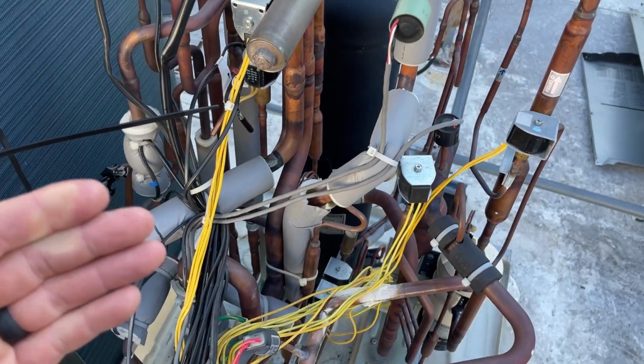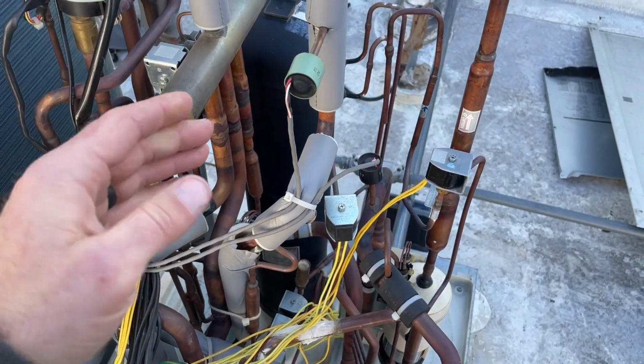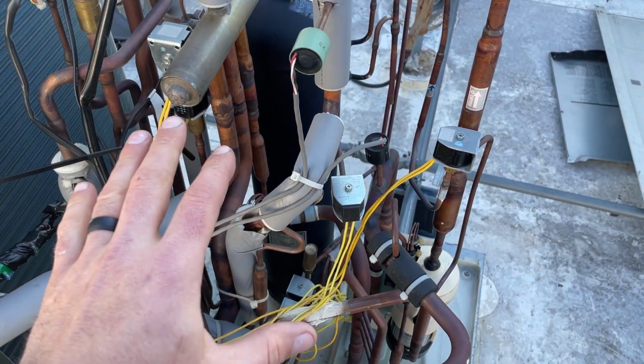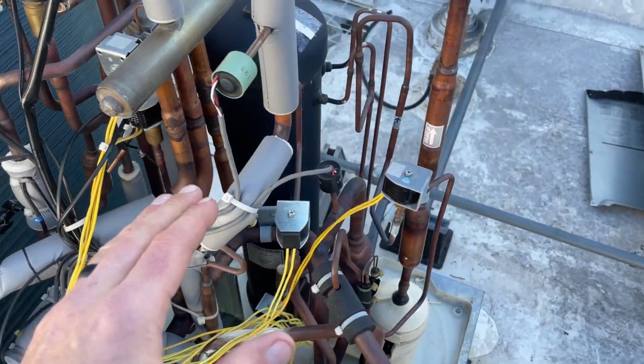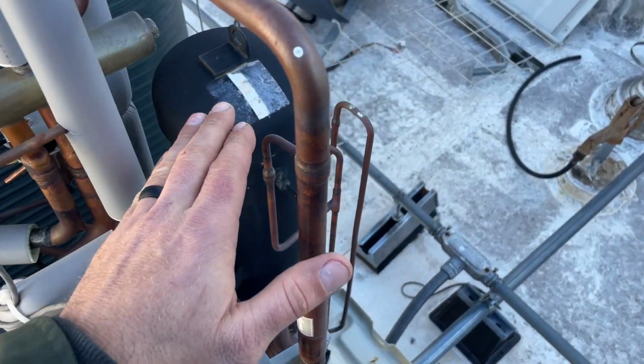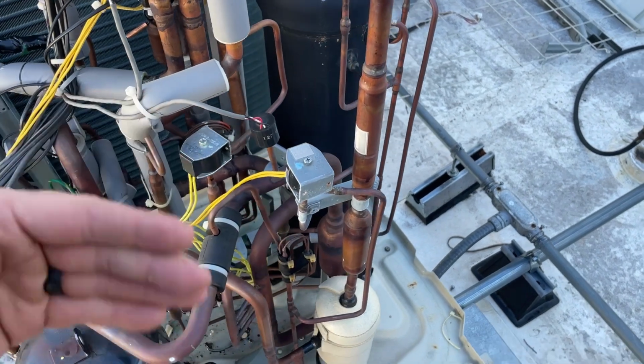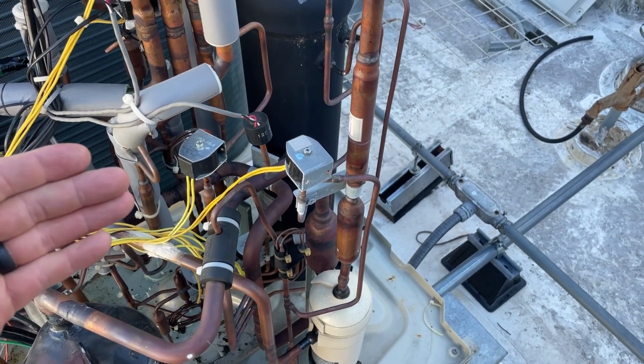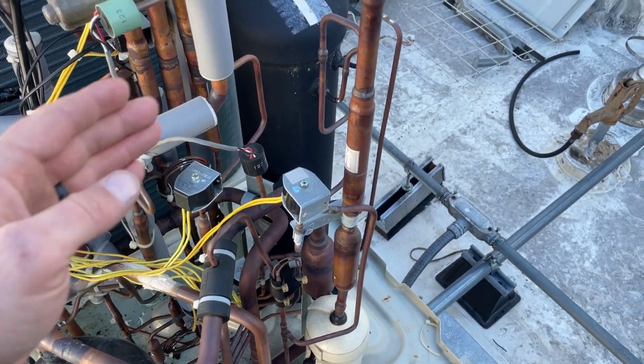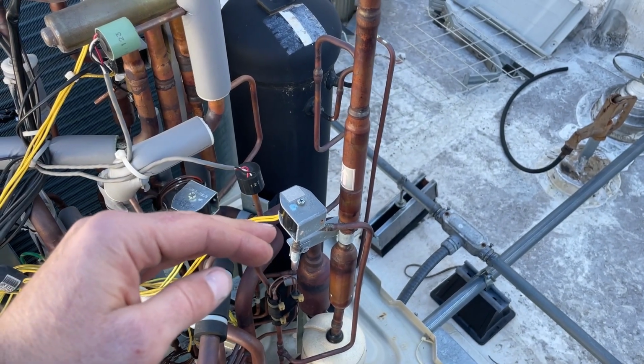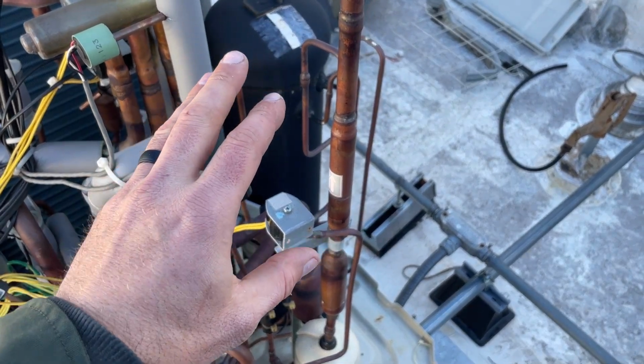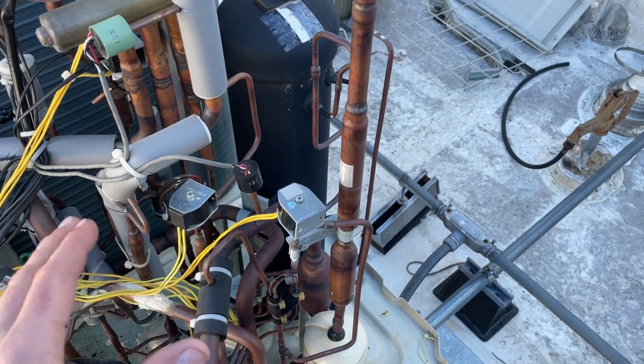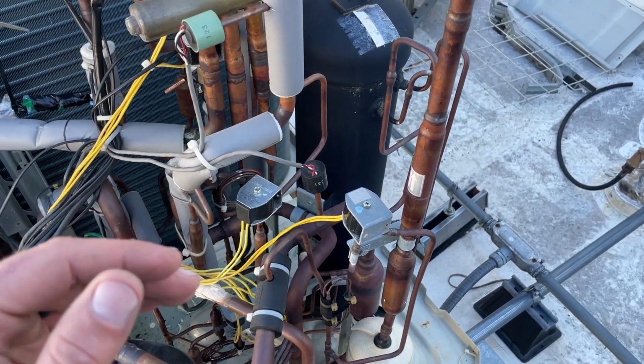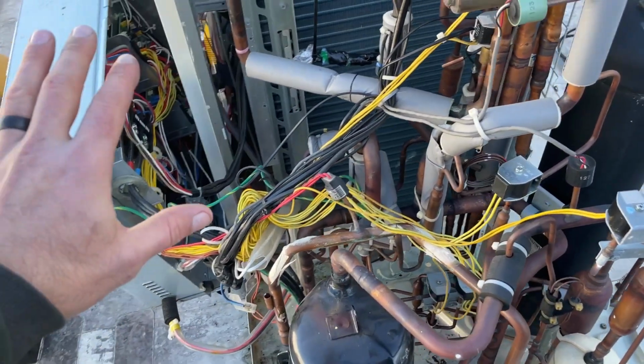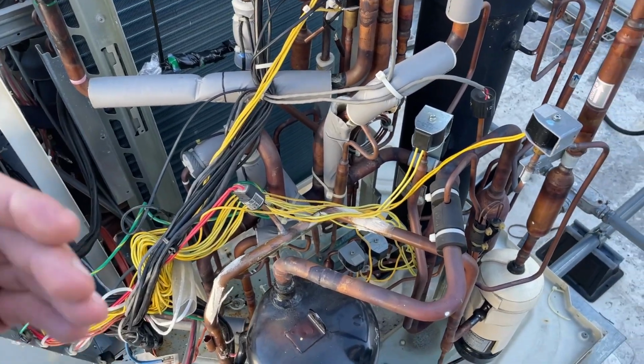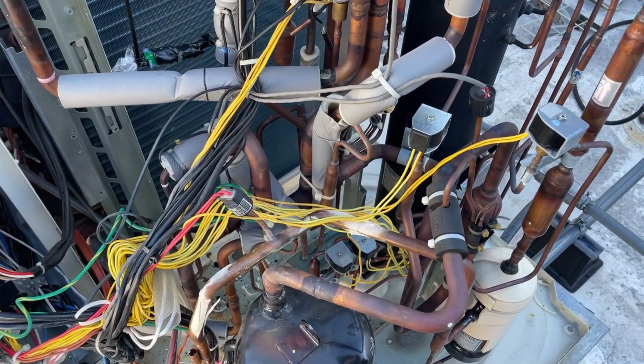But on a system that's very, very highly variable with capacity, you have to have a way to trap refrigerant so that the system can run under really various loads, and then you can release it back into the system. So this is similar, but it's solenoid controlled. It's controlled with an extreme amount of logic. It's not just like a dumb receiver or a dumb accumulator.